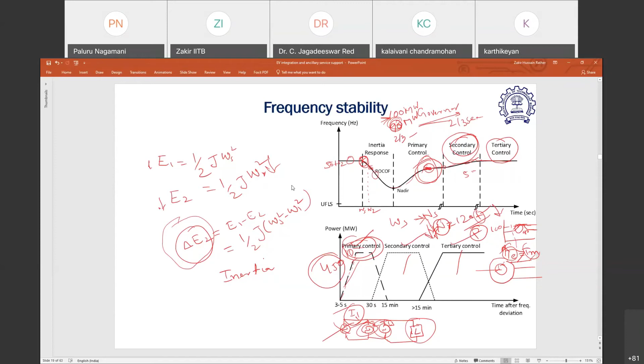And this is what precisely brings us to the ancillary services. Ancillary services are additional grid support services that the grid operator would need to maintain secure and stable grid operation, to cope with the possible contingencies and other imbalances in the grid. Even after perfect scheduling of generation and load in advance, in real-time operation you are not going to have a perfect balance. So to maintain that balance at each and every instant, you have to have backup reserves in the grid.